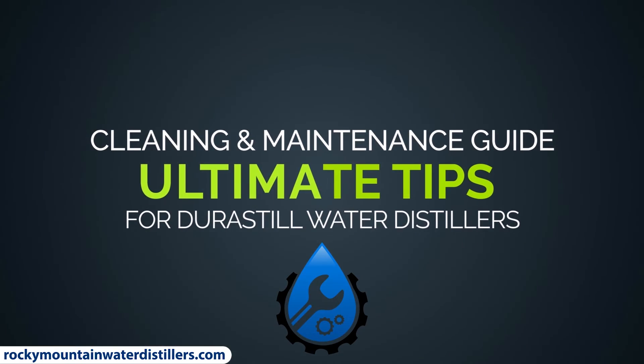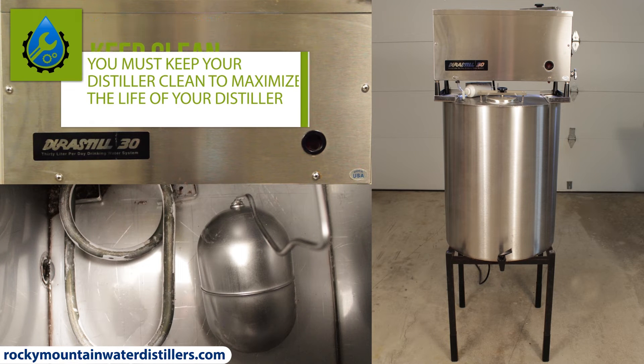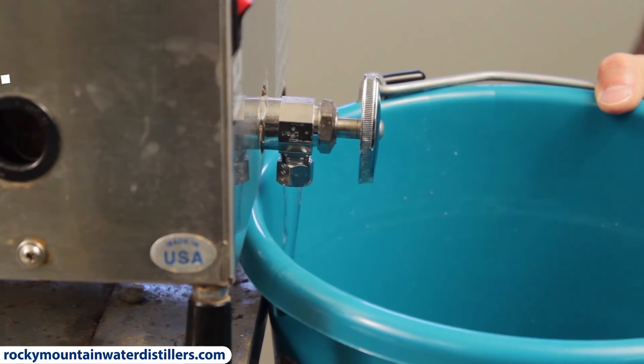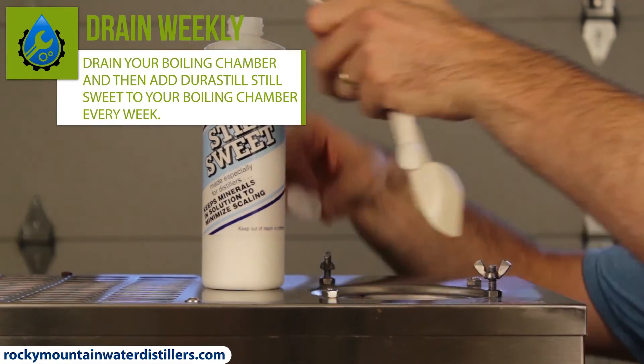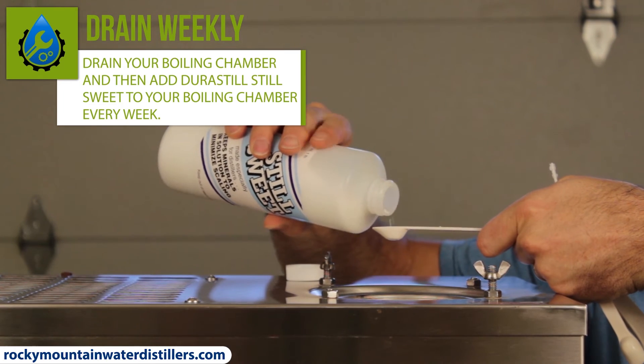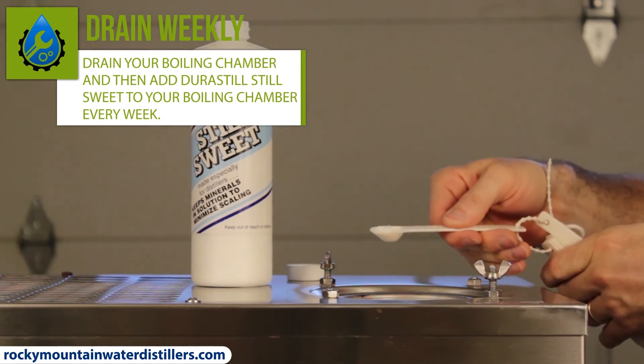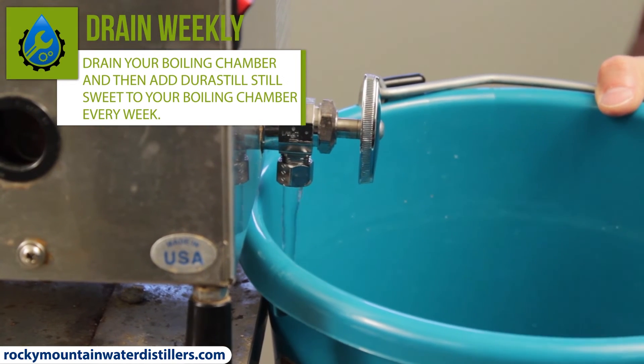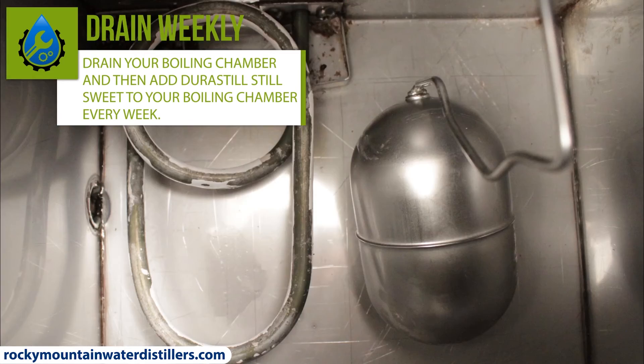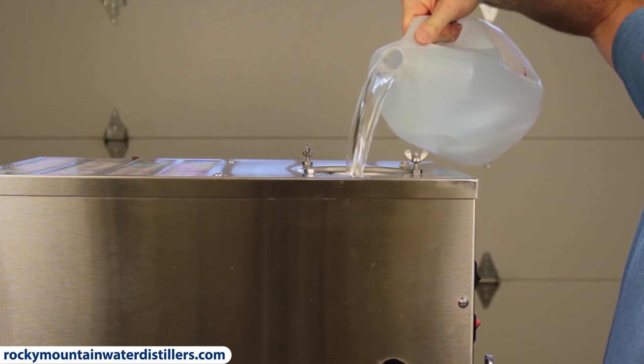Here are the ultimate cleaning and maintenance guide tips. You must keep your distiller clean to maximize the life of your distiller. You should drain your boiling chamber and then add Durastill Still Sweet at least once every month. Even better, the Durastill engineers recommend draining your boiling chamber once per week and then adding Still Sweet. Ideally you would drain it once per week, but I would rather have you drain it once a month than not drain it at all. Draining your boiling chamber will keep it very clean and running optimally. Don't forget to immediately fill up the boiling chamber after.